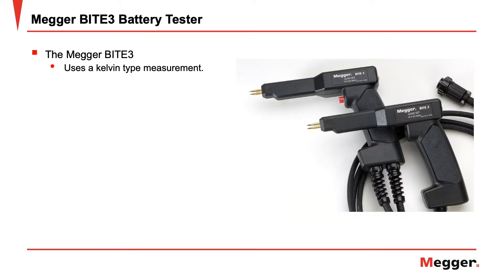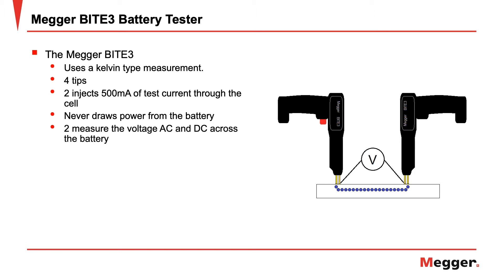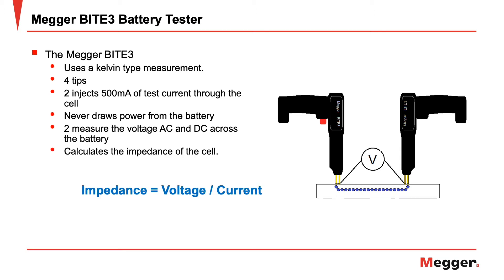The Megger BITE3 uses a Kelvin measurement — a four-connection measurement using a probe with a total of four tips. Two tips inject 500 milliamps of test current through the cell. The unit never draws power from the battery, so it does not discharge the battery. The two other tips then measure the voltage AC and DC across the battery, and the BITE3 calculates the impedance of the cell.